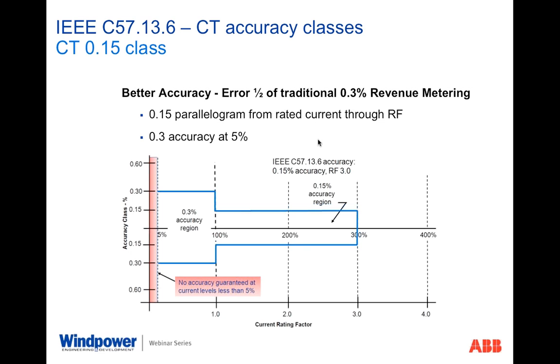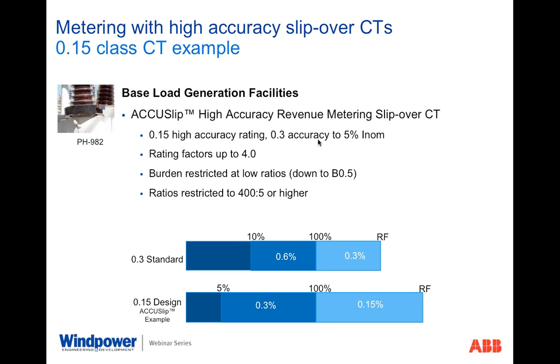So in this application, this was a move in the right direction, getting into a 0.15 accuracy class from the 0.3. But when you look at the reverse power needs with wind farms, this wasn't adequate enough. And so therefore, it sort of left us lacking a product specific for wind farm or renewable applications. Now, this was valuable in the form that it did provide us a standardized format to sell to other applications. For instance, base load generation facilities don't normally have that reverse current measurement need.